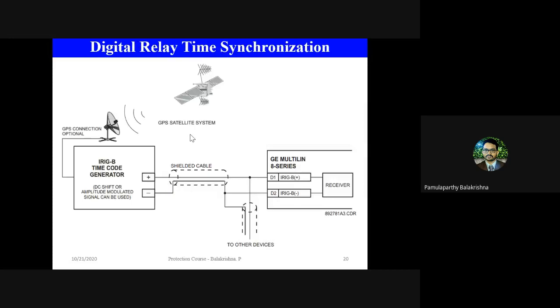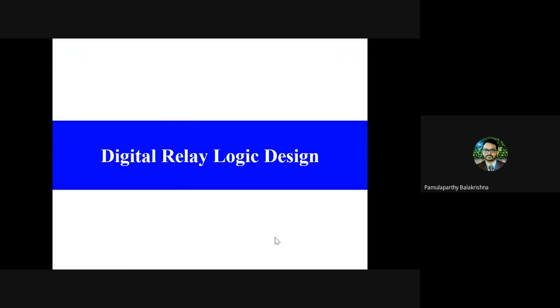Okay, so as I told previously, time synchronization is very critical for digital relays, especially with PMUs and all. The time synchronization input is very critical, and it comes as a satellite input to the IRIG-B timecode generator, which is a separate device in the substation. And from the device, through a cable, all the timing information is communicated to various devices that are present in the substation. Okay, so with that, we have completed the high level features of the digital relays.